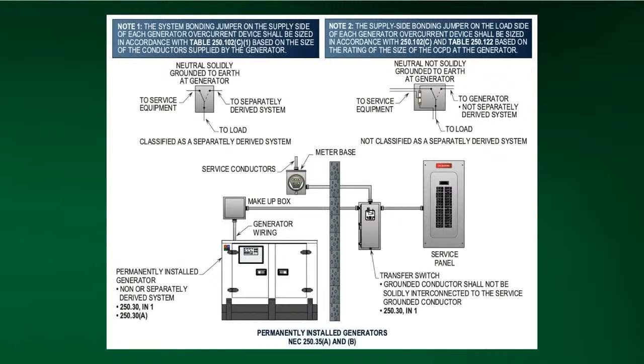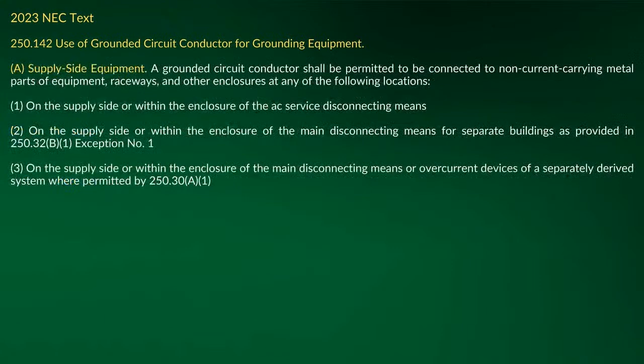And what is interesting about this, we actually have in our generator, transformer, motor, compressor book, in the generator book, we show you this basic stuff here, but we also get down into where we start showing where you have an emergency system, a legally required standby system, and an optional standby system, and how you go about setting all that up, because there's all kinds of different ways depending on how you're coming into the service. Okay. Now, as you come back and you look at this, let me get back here.